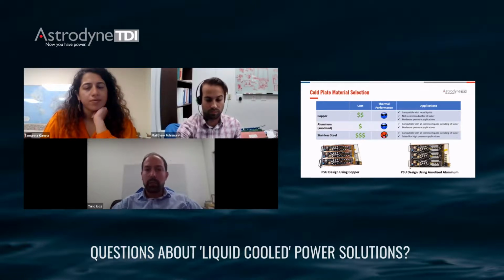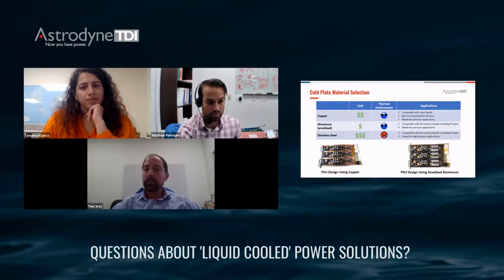Both copper and aluminum are for moderate pressure applications, typically if the line pressure is less than 200 psi. It is not very common, but we've seen applications where the pressure in the line is really high for different reasons. For those high pressure applications, we've seen stainless steel being used more commonly. On the bottom, we show pictures of our power supply in two different configurations. We have design experience with copper and with anodized aluminum. Even though it's rare, we have designed stainless steel heat exchangers, cold plates, and related power supplies as well.